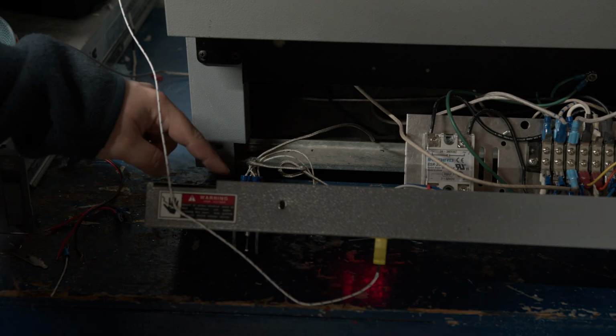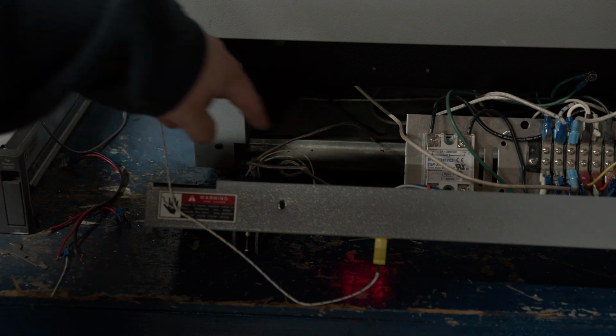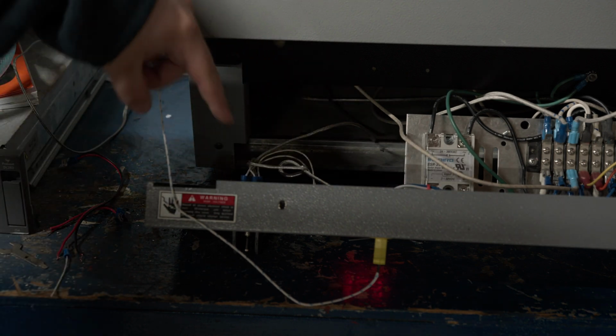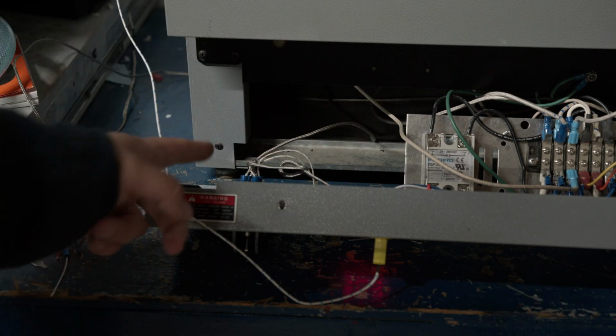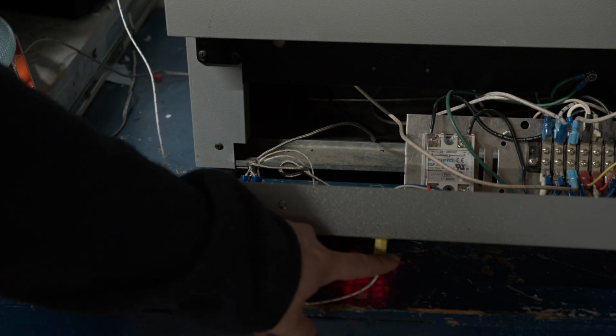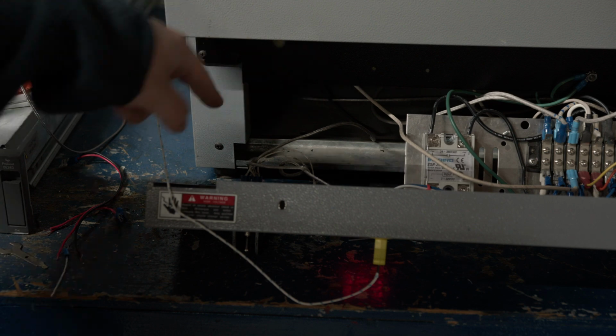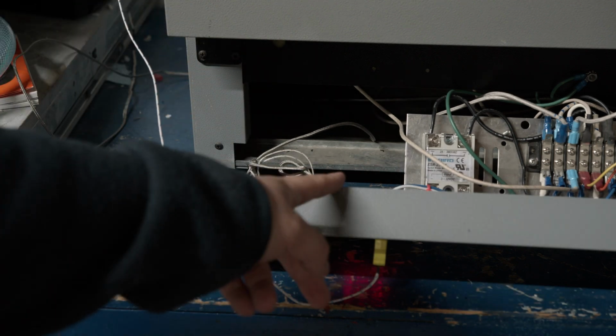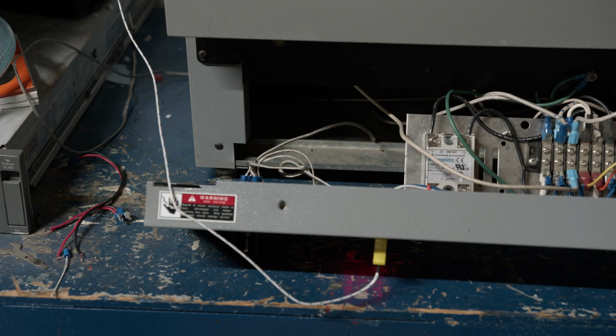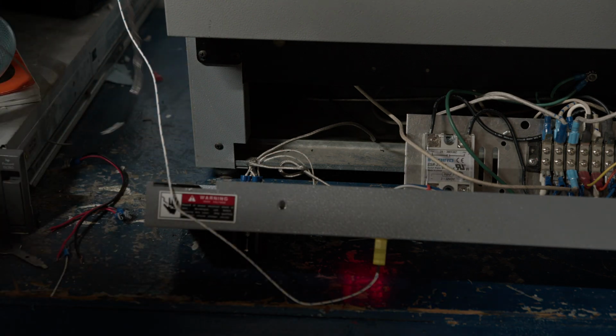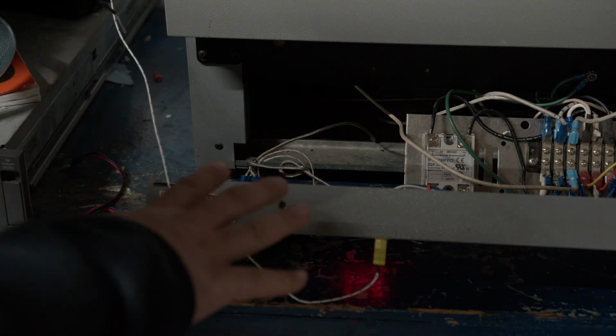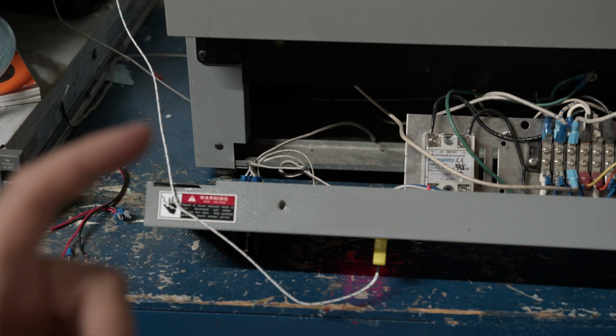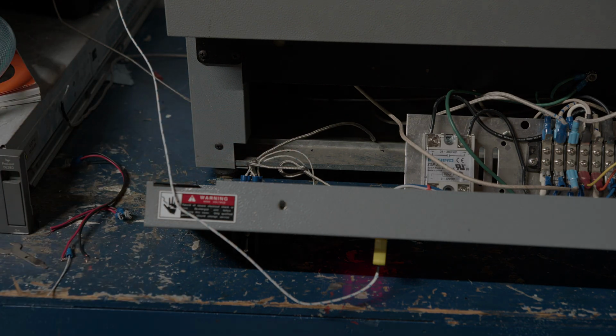Oh, also, for thermocouple wiring, it seems like the switch hasn't caused an issue, but I originally just used some copper wire to go between the switch and the Novus, and also between the switch and this thermocouple connection. And just the connection from the switch over to the instrument panel was giving me several degrees of inaccuracy using copper wire. So you want to use some off-cut thermocouple wiring for anything in line with a thermocouple. Even a couple inches of copper wire is going to cause you problems.